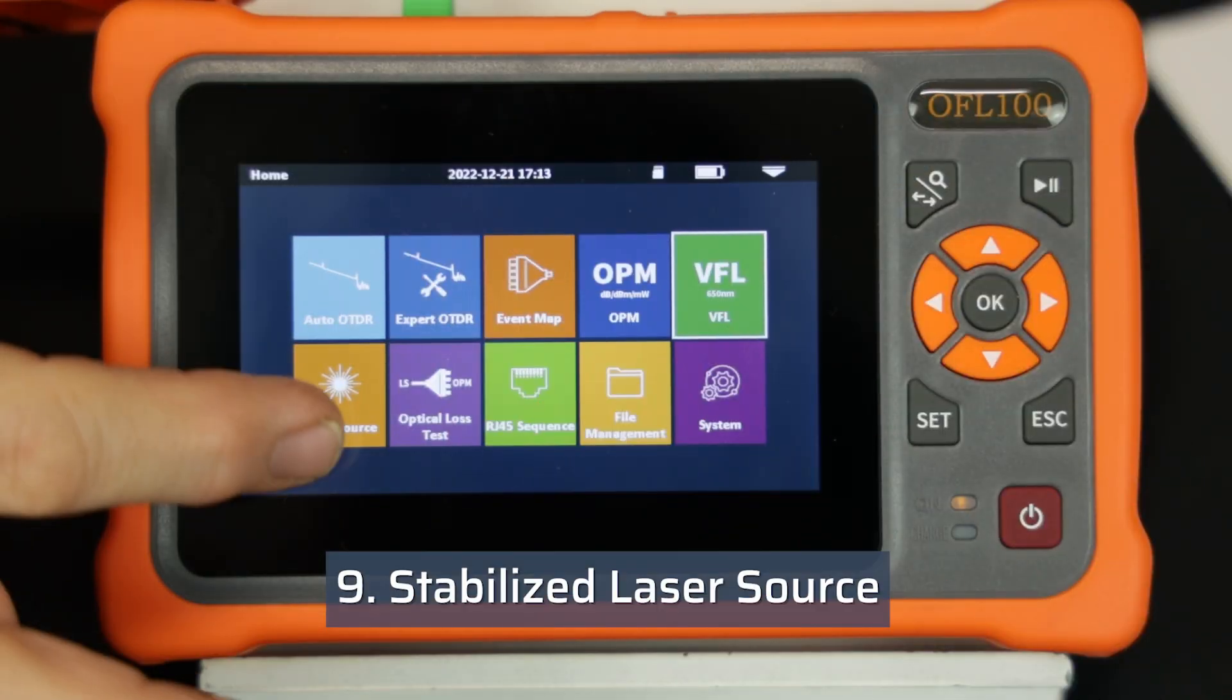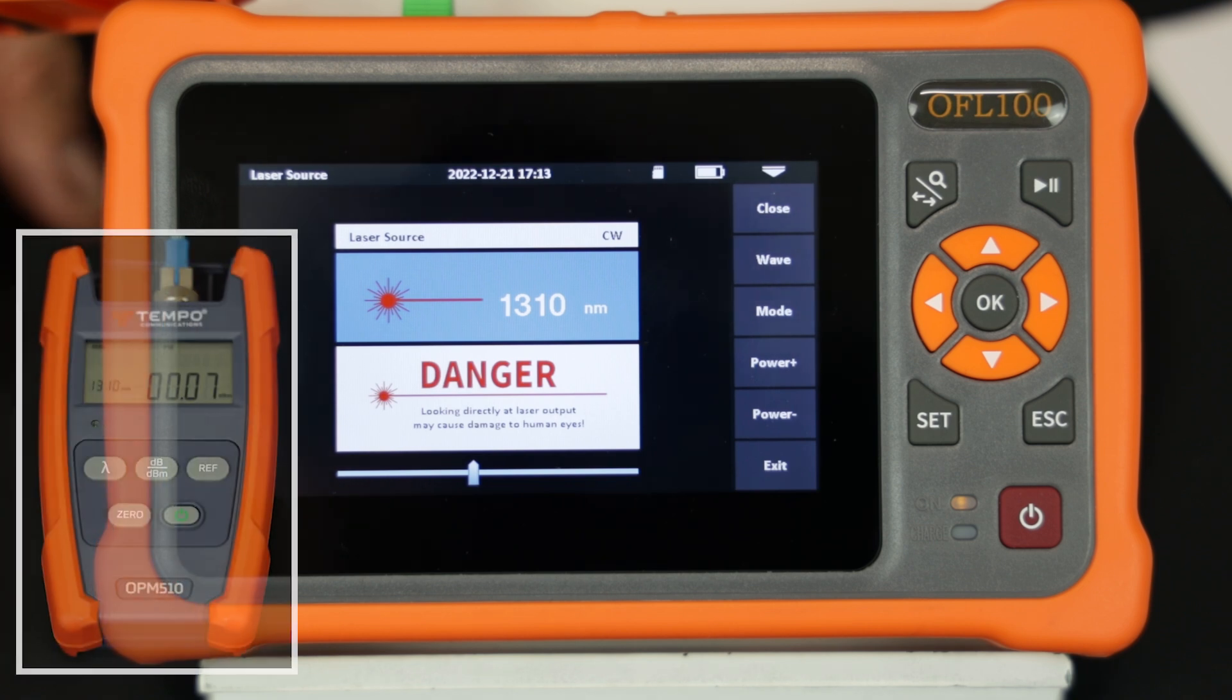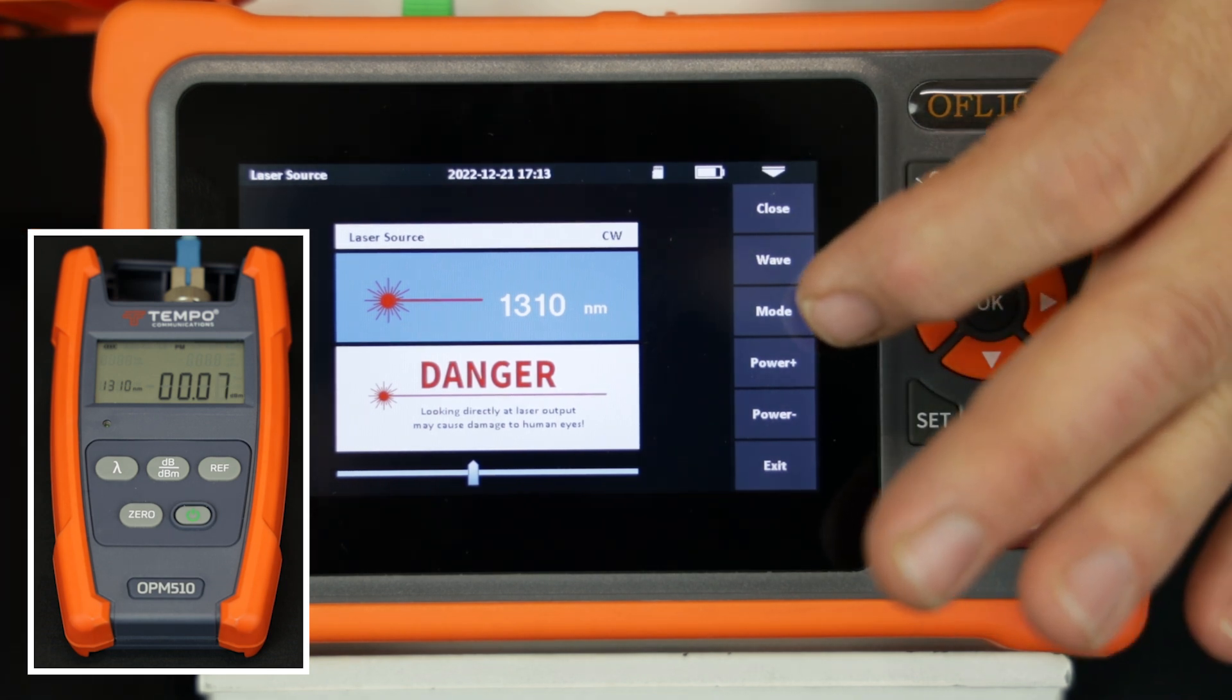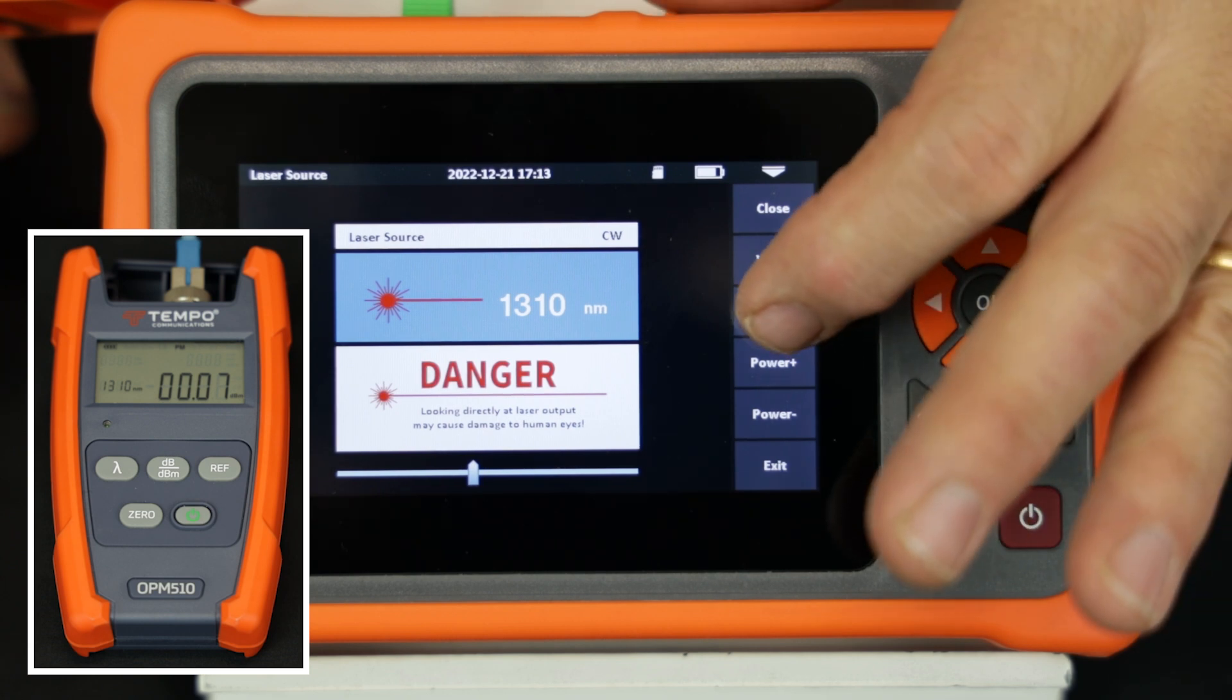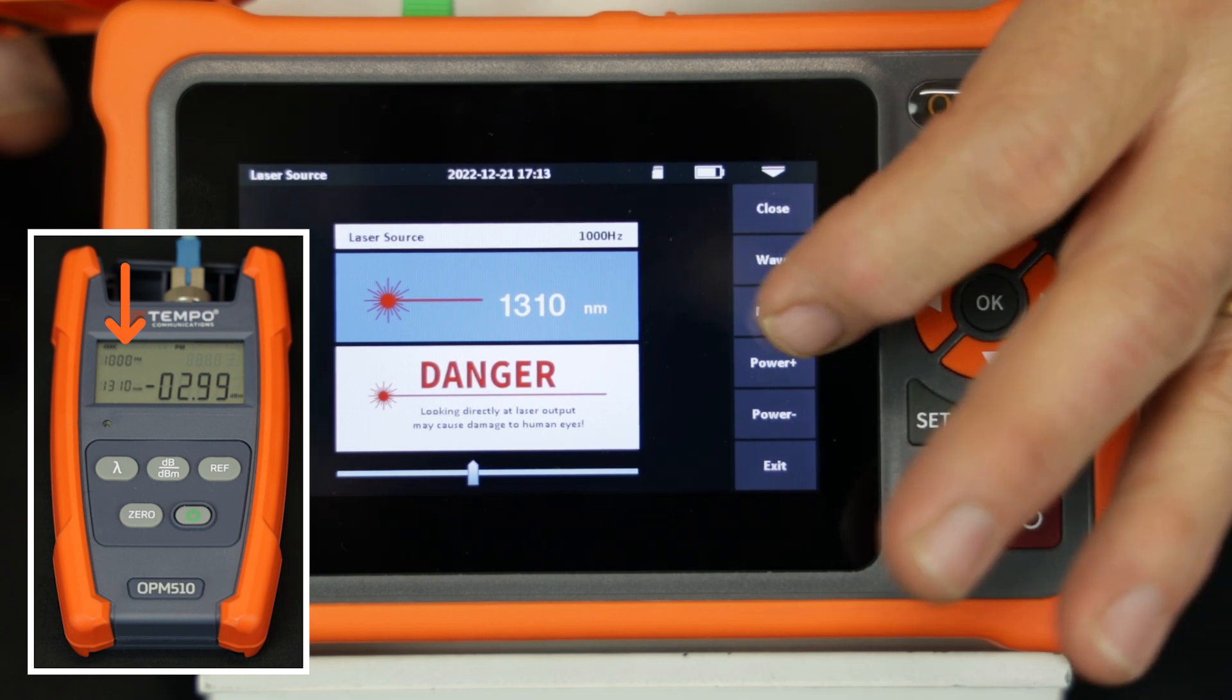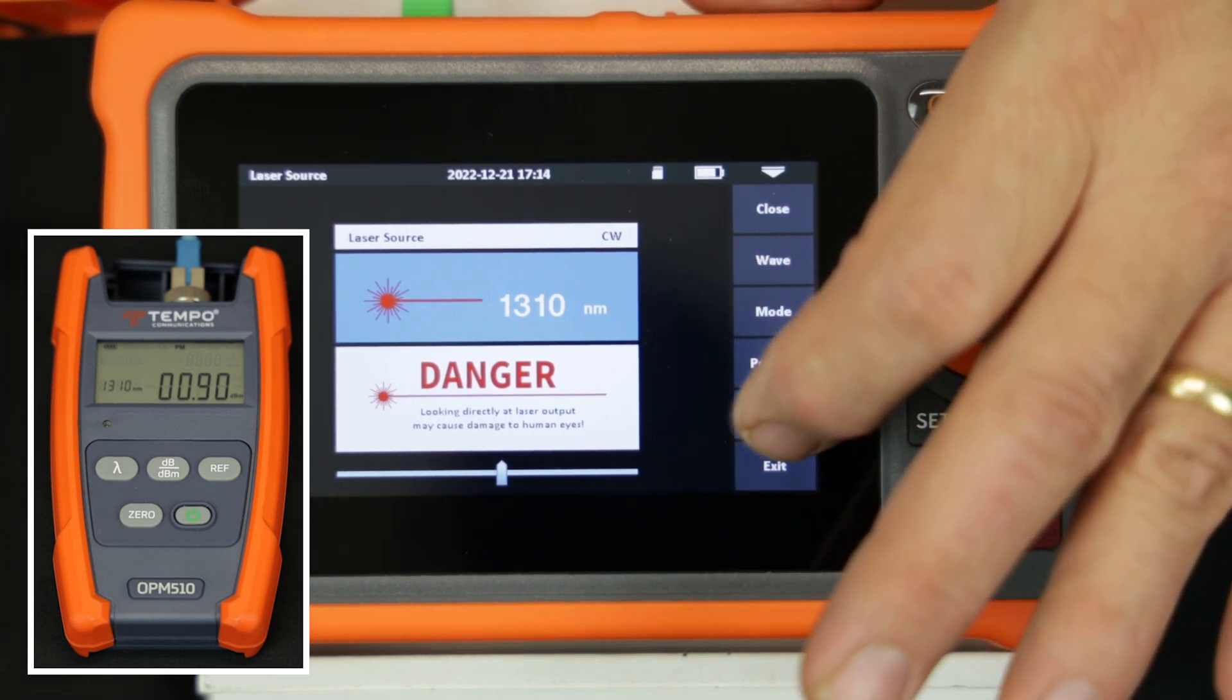Select the laser source from the main menu and use the OTDR port as a stabilized laser source. The laser source is turned on and will be active. The output power is displayed on the OPM510. The wavelength can be toggled between 1310 nm and 1550 nm. Make sure that the OPM510 is on the correct wavelength. The mode of the laser source can be constant wave CW, 270 Hz, 330 Hz, 1 kHz, and 2 kHz. The output power can be increased or decreased as desired.